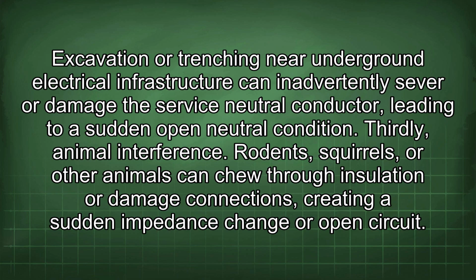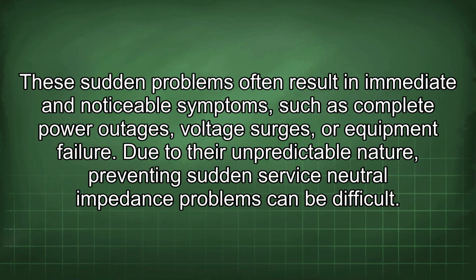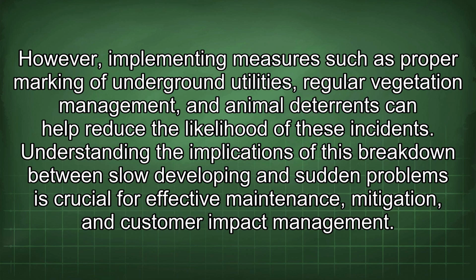Thirdly, animal interference. Rodents, squirrels, or other animals can chew through insulation or damage connections, creating a sudden impedance change or open circuit. These sudden problems often result in immediate and noticeable symptoms, such as complete power outages, voltage surges, or equipment failure. Due to their unpredictable nature, preventing sudden service-neutral impedance problems can be difficult.